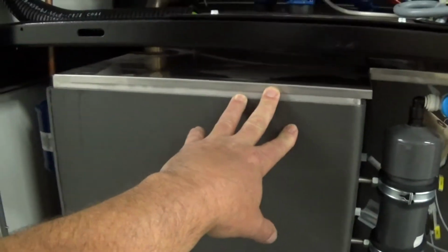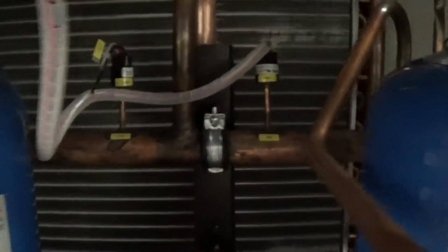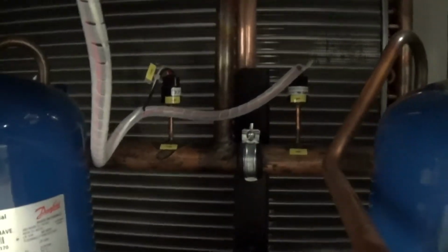What is relevant is your primary holding tank here, your primary brazed plate heat exchanger, this blue item here, that's your solenoid valve for the hot gas bypass for capacity control, your refrigerant sight glass here, and we have two low pressure switches. One of them is for a safety, and one of them is to control one of the other controller functions. Then you have your high pressure switches here. One of them is for fan switching. The other one is your manual reset if you were to go into a high pressure alarm condition.